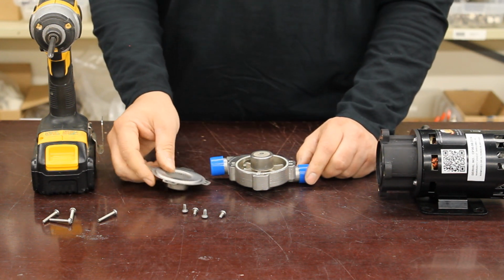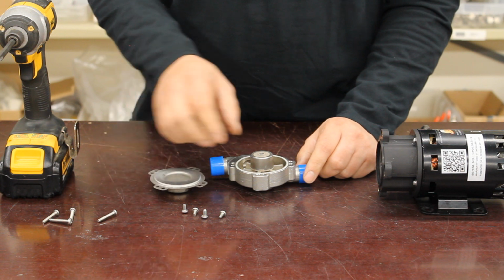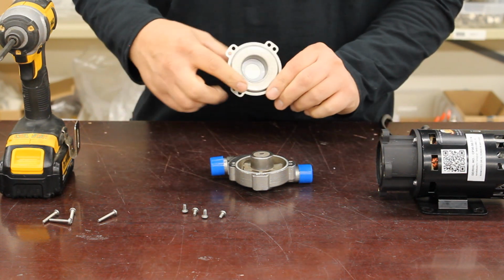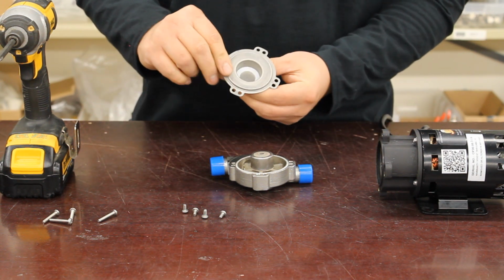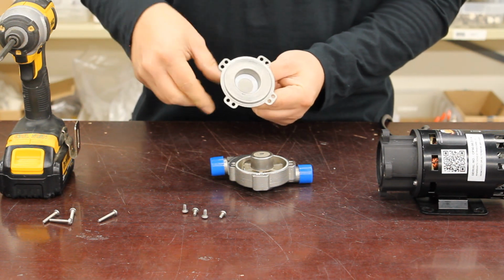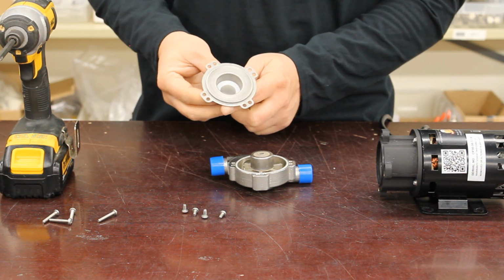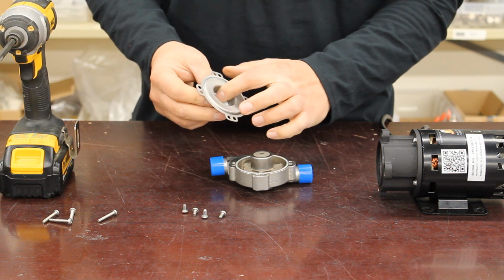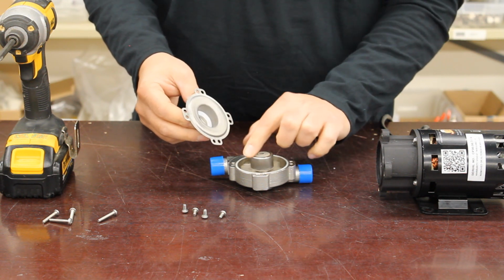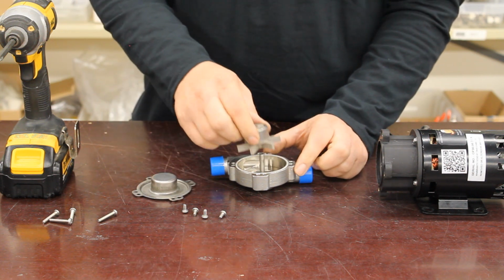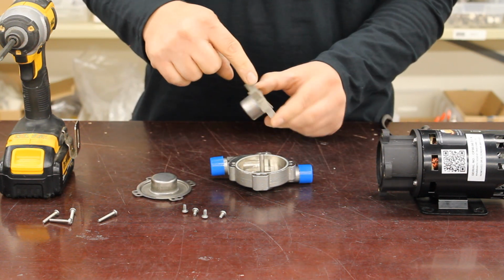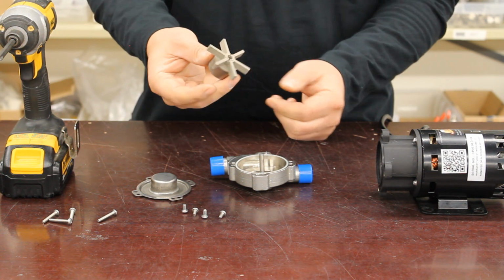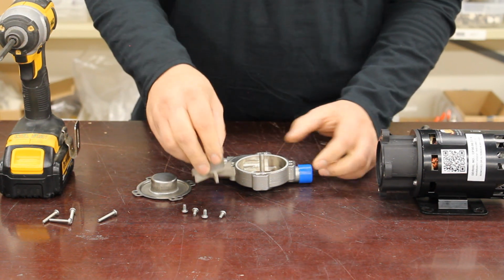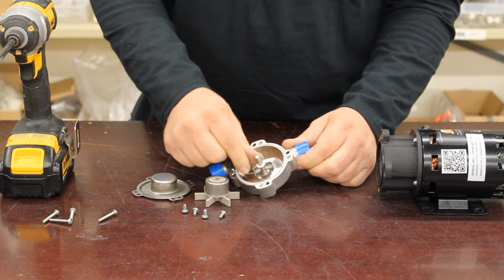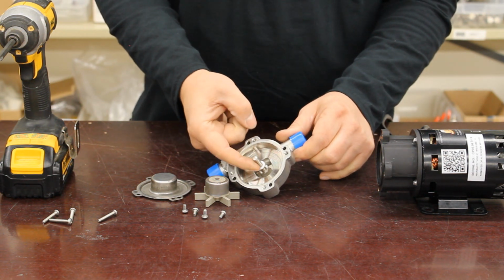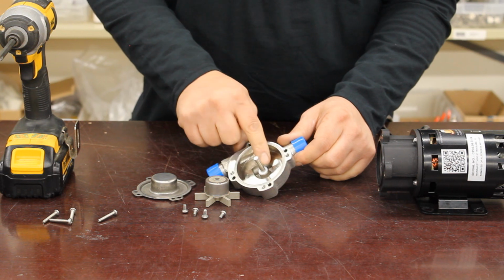All right, so while we have this open, why don't we just go over the parts that are inside here. First of all, this is the back cover plate of the head. This is the large thrust washer. It's a plastic washer that goes in the back, and that provides a bearing surface for the impeller to ride on. Then we have the impeller. This is the impeller magnet and the impeller blades itself. This is one piece unit that doesn't come apart. And then the last piece is the thrust washer that goes on the front of the impeller on the impeller shaft.